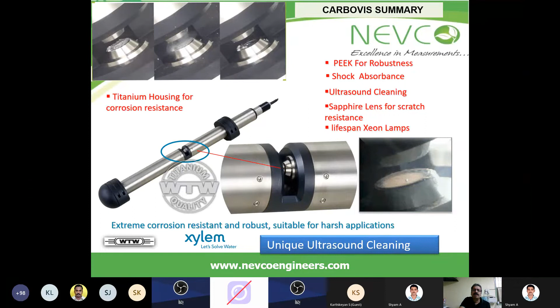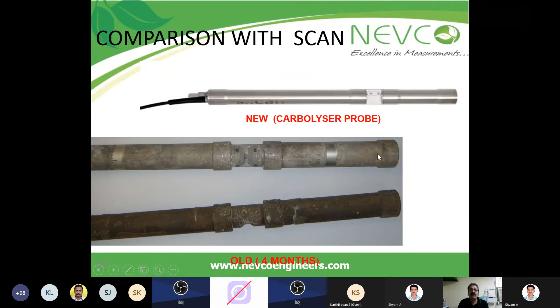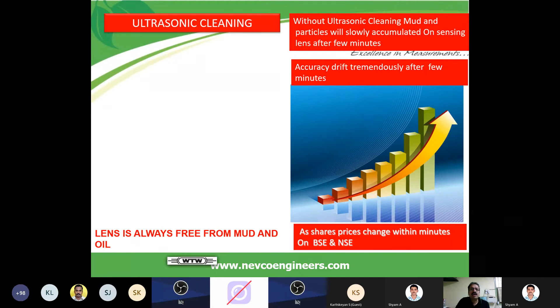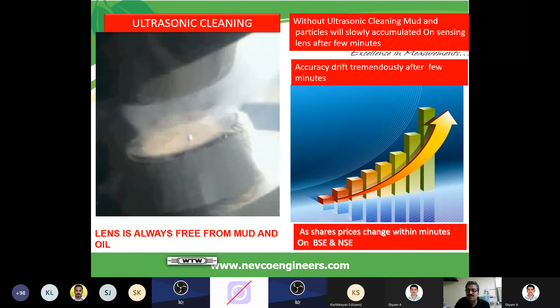This is an example of our competition with another company which uses an SS probe. After some days, this SS probe has become black, fully oxidized and corroded, and your values will be very erratic. Whereas ours has ultrasonic cleaning, so the lens is always free from mud and oil. If you have mud on the sensing lens, the drift of the measurement is continuously high as it accumulates. After a few minutes, you will see it change, like share prices changing within minutes on the BSE and NSE. Similarly, the readings will be fouled in no time.